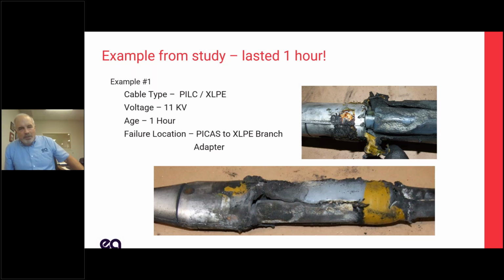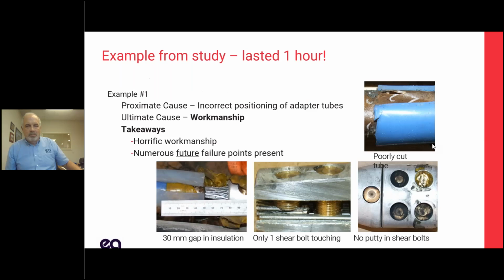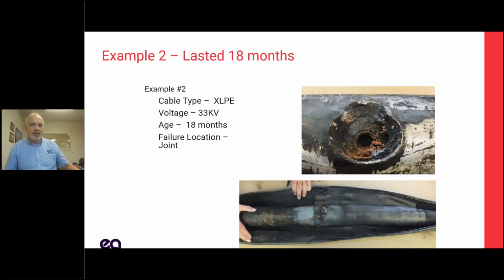A couple quick examples. Here's one of the cables from the study. It's 11 kV. It lasted 1 hour. We look at the cable. Lots of problems. No putty in the shear bolts. Poorly cut tubes. Shear bolts, only one of them touching. This thing would have failed for any one of these reasons, and it failed for a variety of them. So, workmanship right there.